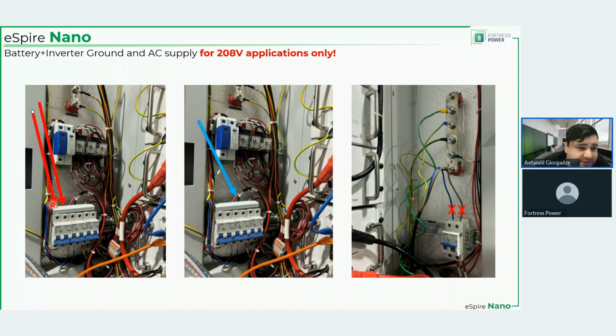With this cable, the transformer is energized, but that power cannot flow anywhere because on the other side you have no cables. And I mean, if you wanted, you could remove these cables. It's just, from my point of view, additional work. So you connect 208 volts here, and you have 208 volts for the AC circuits, like those converters that I was talking about, and the HVAC. If you connect 208 volts here, and again, nothing will be connected to the breaker that we usually use for AC supply when there's 480 volt present. And this is only for 208 volt applications, never 480.